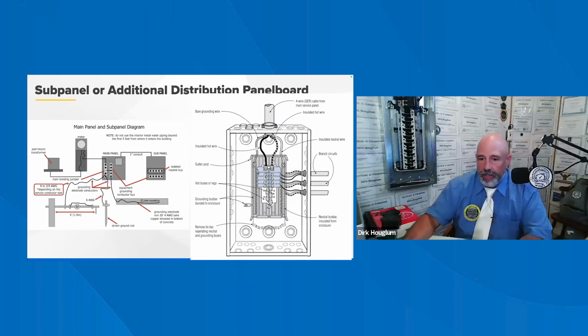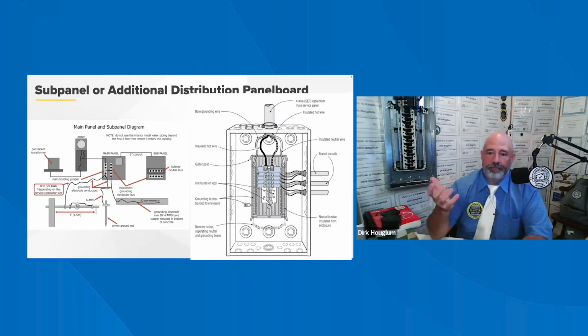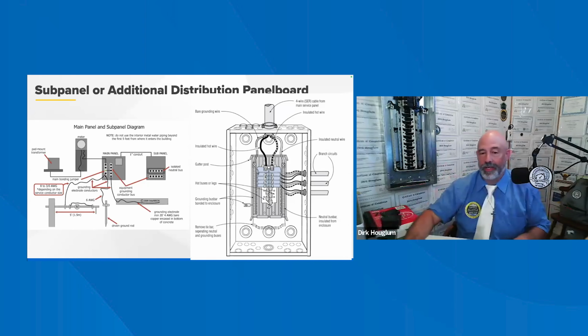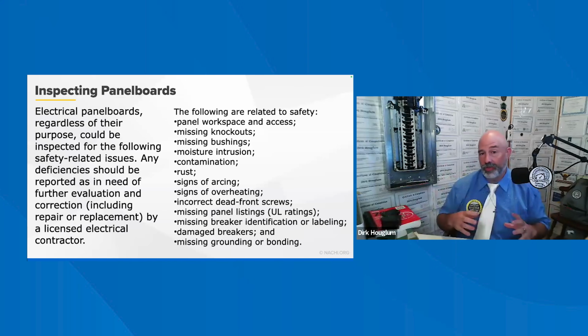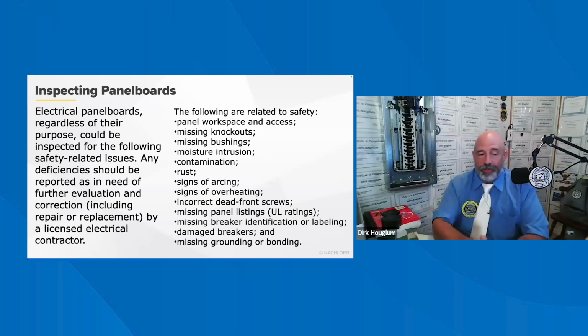So, sub panels or additional distribution panels can't have the grounded conductors, the neutrals, and the equipment grounding conductors, the bare wires, terminate together. The neutral and the bare grounding wires must be separated in the sub panel. I keep going over that and over that because I need to get that drilled in your head, because so many times I've done inspections on houses where other home inspectors didn't even mention it. My house was one of them. But again, our house was built in the 1980s.